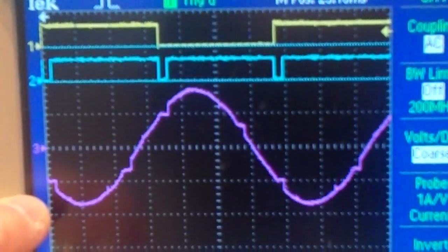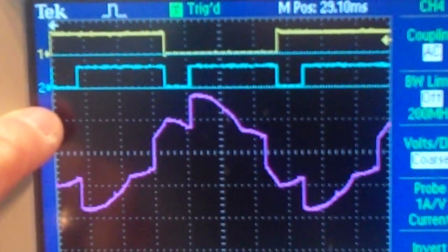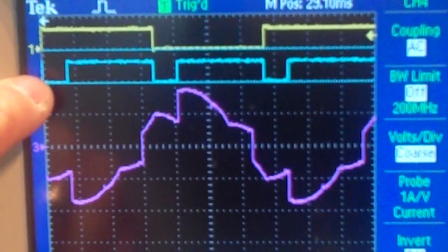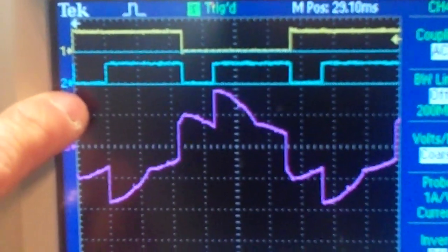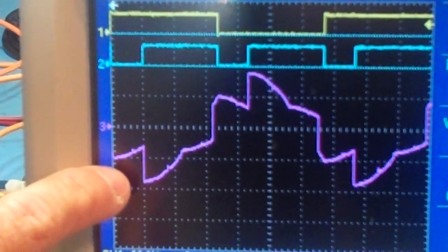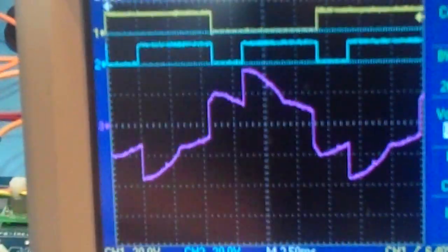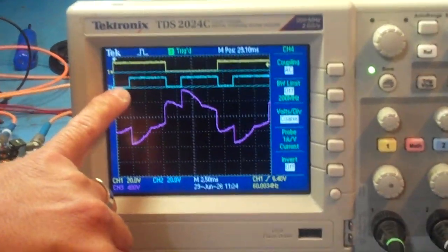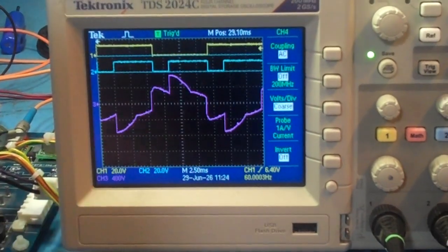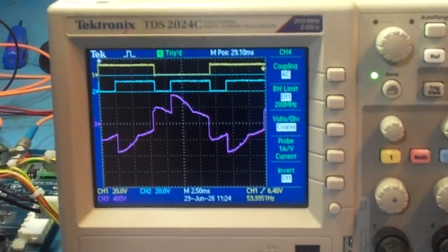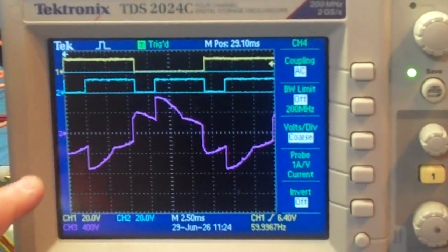Go ahead and start coming down. See how that stops. Go ahead. Keep on going. There, right there. Right there is good. You notice how that vertical line coincides with that, and that's part of the commutation notch. And we're only looking at this right here. It's the A reference. If we had the B, we will have it here, and if we had the C, we will have that on the different commutation notches for all the 6 SCRs.